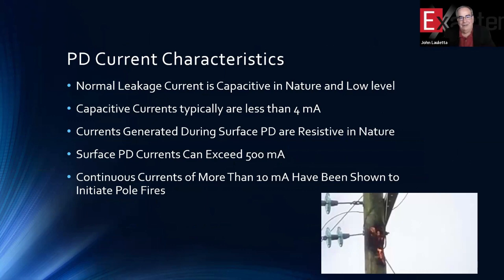So everything has a leakage current. We all know that. It's because of the AC nature of the system. We're really just above ground. We're not away from ground. So there's always currents flowing down the pole from the energized equipment, but it's usually less than a few milliamps, and it's very capacitive in nature. So if you have a grounded pole and can look at the ground wire itself, you'll always find some leakage current from the system above. And in high humidity times, that leakage current may go up a little bit. But when it stays low and capacitive, the poles seem to withstand that pretty well.